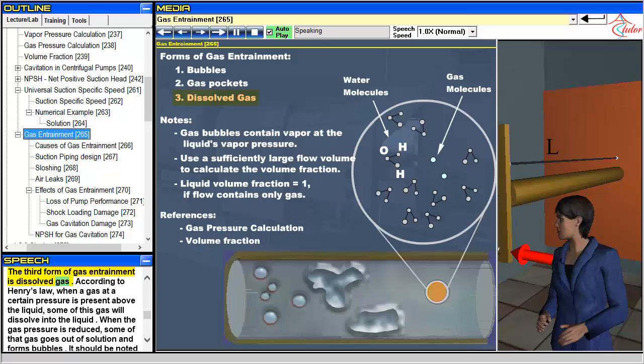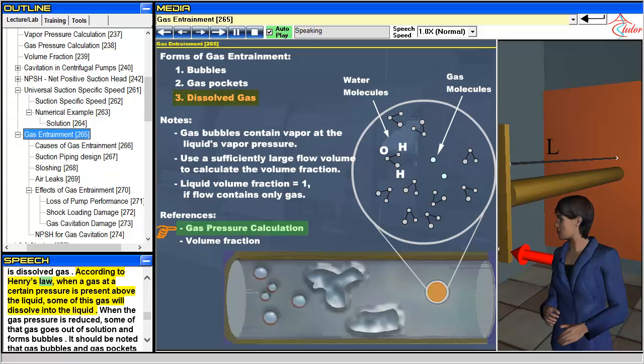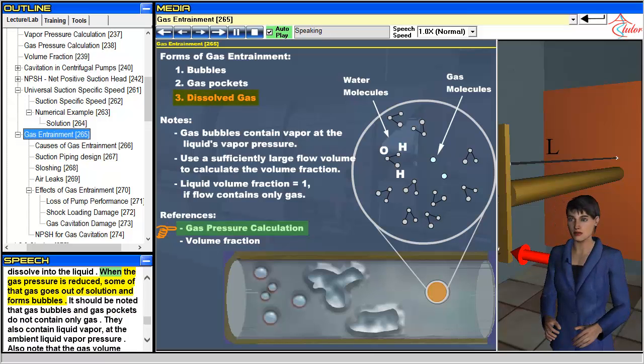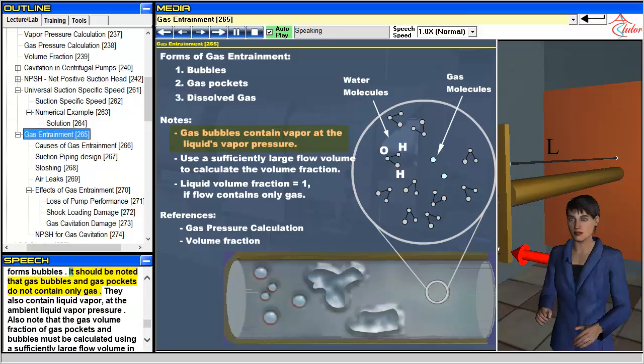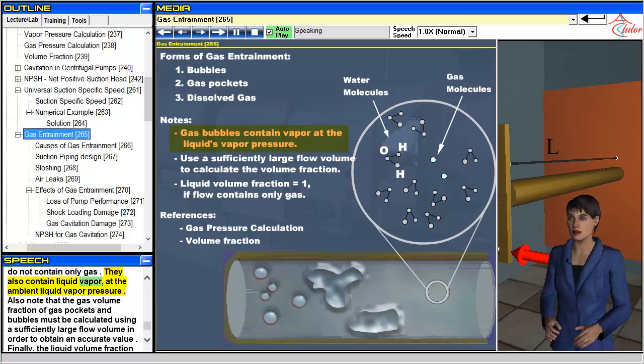The third form of gas entrainment is dissolved gas. According to Henry's law, when a gas at a certain pressure is present above the liquid, some of this gas will dissolve into the liquid. When the gas pressure is reduced, some of that gas goes out of solution and forms bubbles. It should be noted that gas bubbles and gas pockets do not contain only gas — they also contain liquid vapor at the ambient liquid vapor pressure.